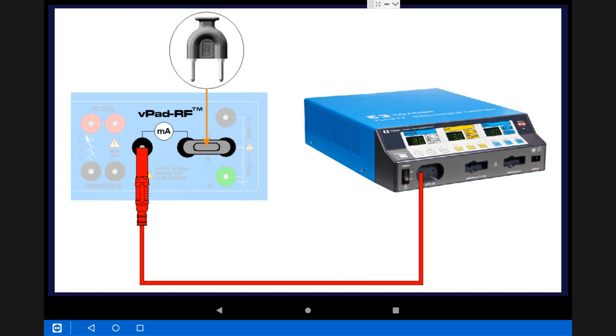One final step for leakage of checking the macro. Check for leakage on macro, and again, we're in tolerance and we're good there. So now we're going to return the generator controls to the previous desired settings, and we're going to move on to the next section of our testing. From here, we're able to go ahead and save the ESU test.